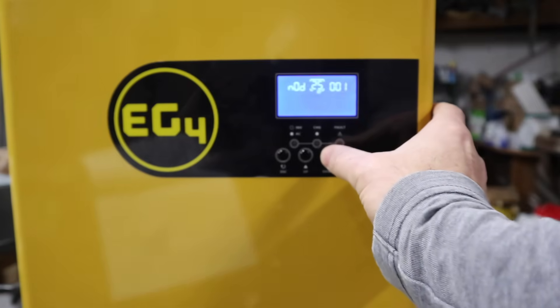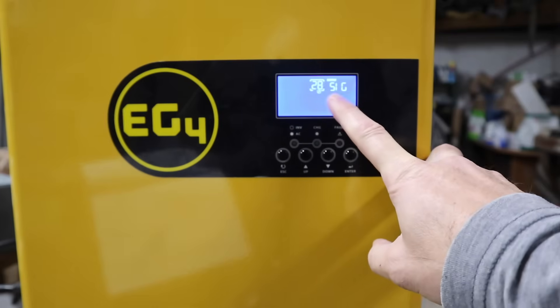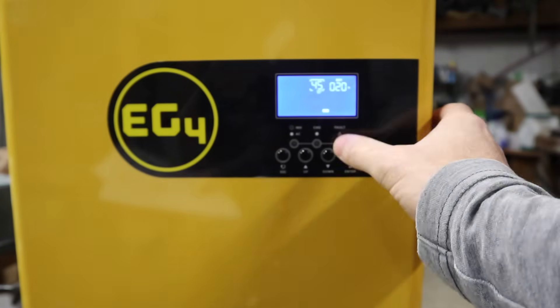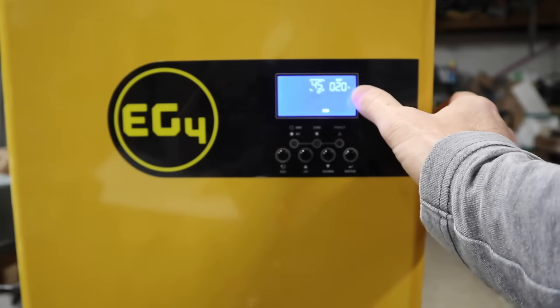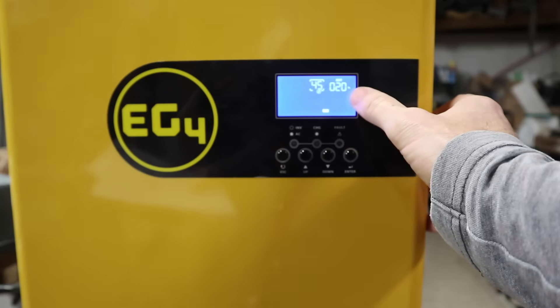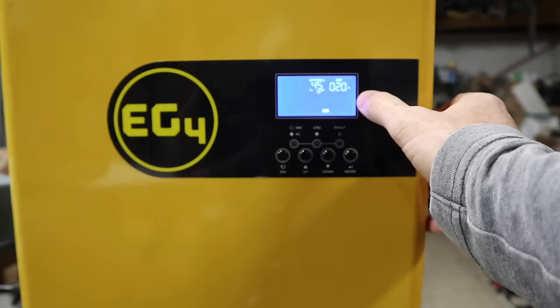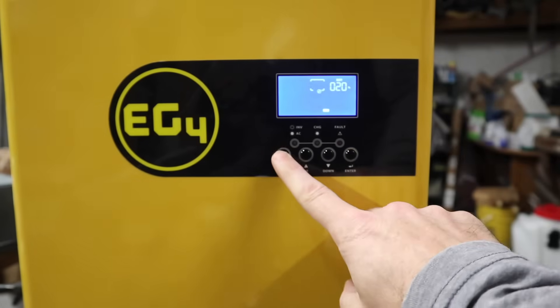Then go down to setting 28, which is where you set the parallel settings. Since we just have a single inverter, set it to SNG. The last setting is number 45, where you set the battery to cut off at 20% state of charge. This is debatable, but it's usually where EG4 recommends to conserve the warranty. That said, lithium batteries can really drain down to 0%. Those are all the basic settings you need.